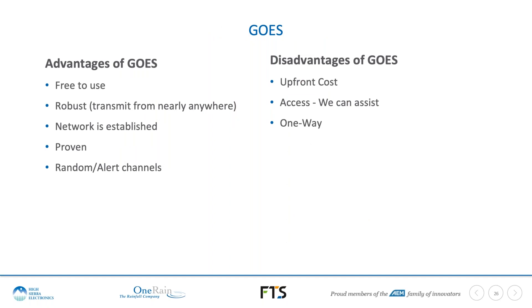GOES advantages: the biggest is that it's free to use — once you're granted access and given a channel and ID, there is no annual cost. It's extremely robust, proven, and well-established. The Random channel allows event-based transmission. The disadvantage is that the equipment has a larger upfront cost compared to some other options. It is also one-way communication. Access to the GOES system is broadly available and we can help advise on how to obtain it.